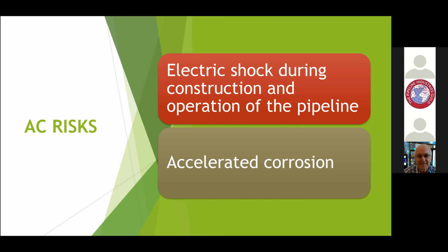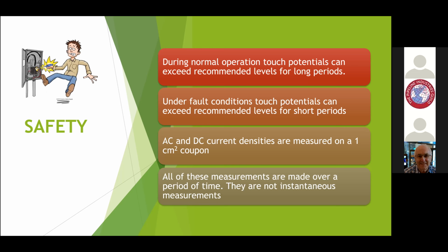And the second risk is accelerated corrosion. During the normal operation of the train, it's quite possible for what they call touch potentials to be above the recommended levels. I've been careful not to put a value in for the recommended level because it varies for different countries and different regions, but it's normally between 50 and 60 volts, something like that.